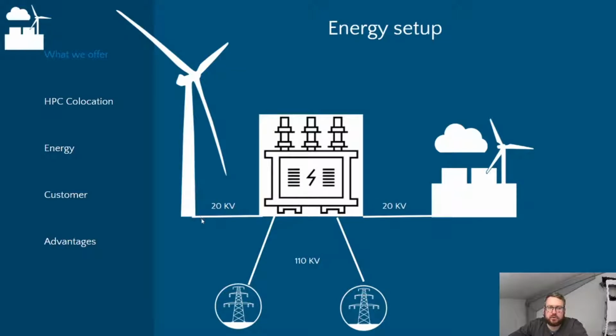Running your own grid has some advantages, including that you're able to supply energy to any commercial company. This is represented by our Colocation.Green product. The benefit for actual data center operation is that our switchyard is connected to 2 redundant 110 kilovolt settings to the standard grid, so even if we didn't have any energy generated, we could still keep running over one of those backplanes.